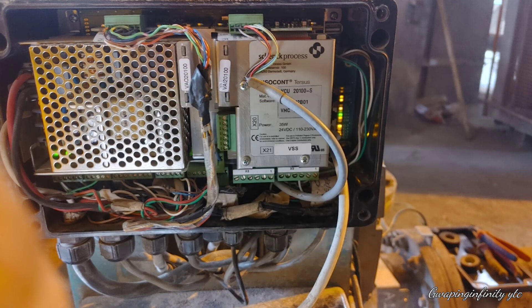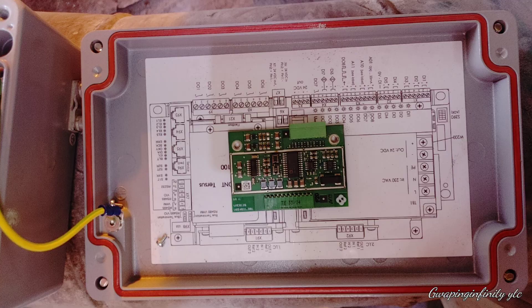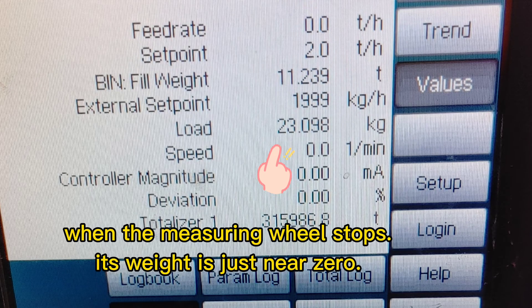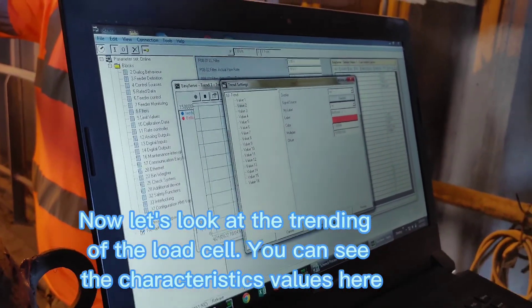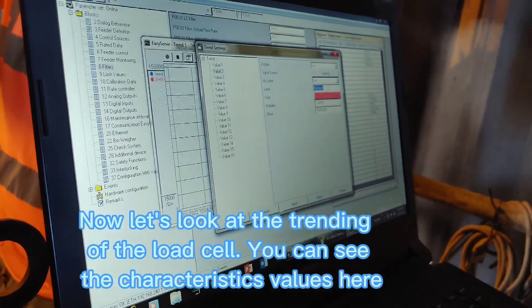The load cell card needed replacement due to a bad signal. At first we didn't replace it, but the load cell was replaced with confirmation that weak LC signals were the root cause. The load cell circuit board was replaced. When the measuring wheel stops, its weight is just near zero. Now let's look at the trending of the load cell — you can see the characteristic values here.